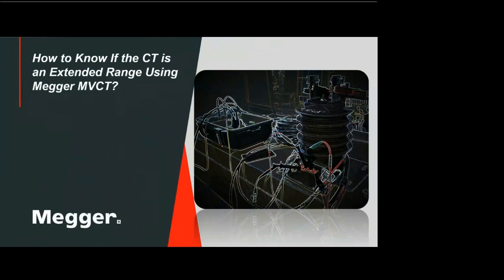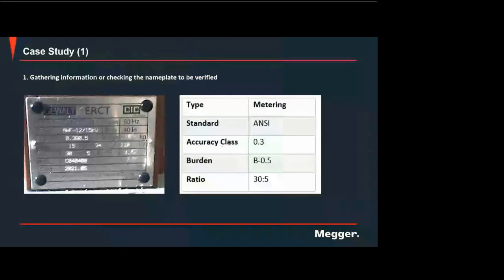Now, we would like to share these case studies that we have on how to determine if the ERCT or the CT is an extended range. Okay, so first thing that we did, we gathered information or checked the nameplate to be verified. So as you can see here, yes, this is an ERCT. But how would we know if this is a real ERCT? It displays 0.3B 0.5, so meaning the accuracy class is 0.3. So we are expecting 0.3% here, and the burden is 0.5, and then the ratio is 30:5. Okay, so we are verifying this 0.3 here.